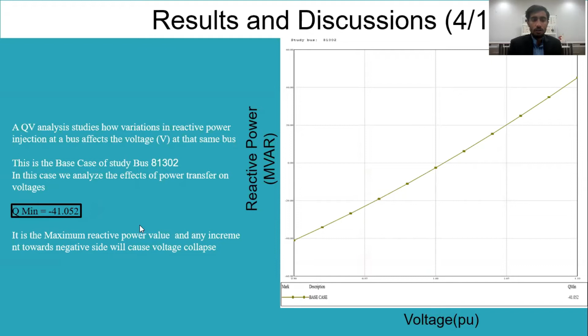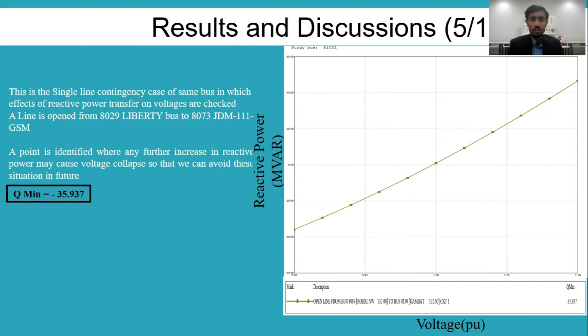And this is a single line contingency case. In this case, we find that Q minimum, minus 35.937, is the maximum value of reactive power. After that, if we inject more reactive power, then it may cause voltage instability problems. So these are the PV curves that are used to find the voltage instability and the critical voltages, critical points. After that, if there is any increment, then the system's voltage might collapse.